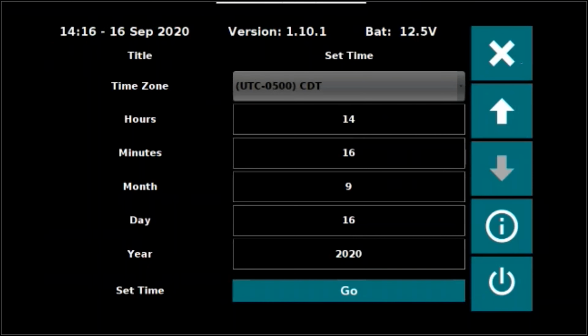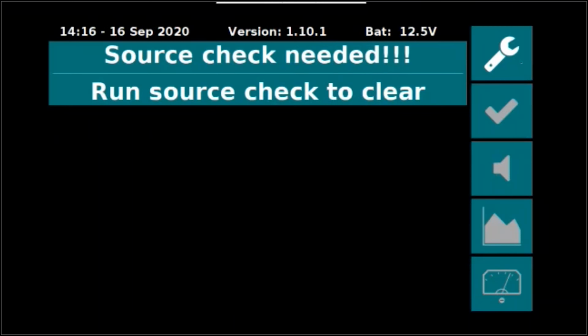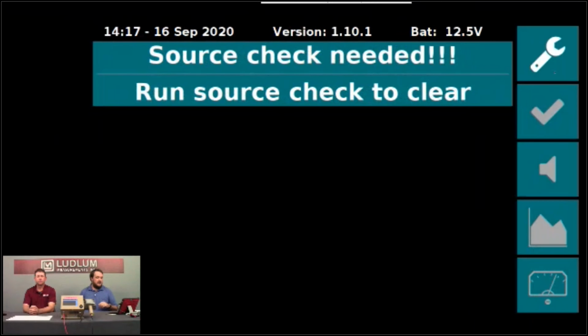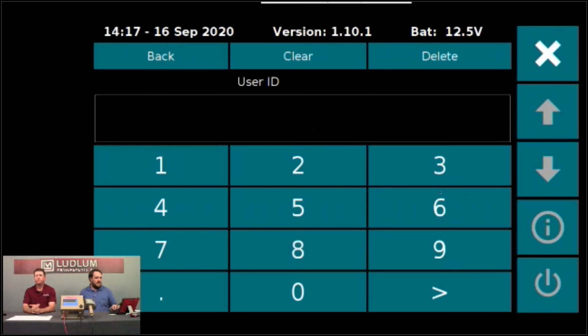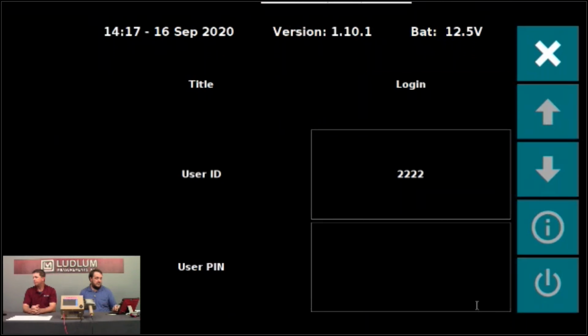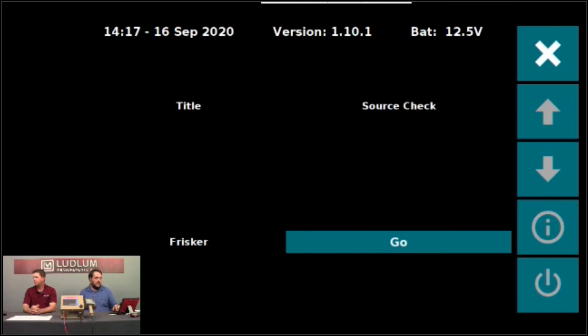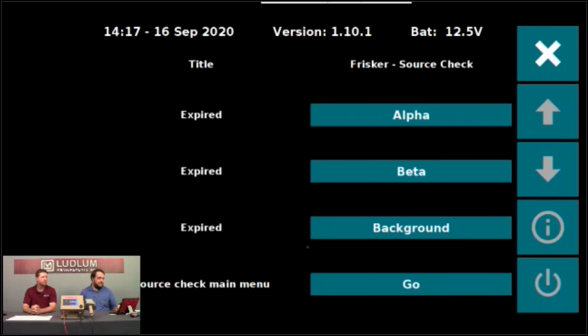So if I go back to the main settings, I've enabled the source check. So now the unit is unusable while the source check is expired. You can go into the settings menu again, or click the settings button, and this time go in as the source check user. And here you'll pick the detector you need to do a source check on. In this case, there's only the one. Again, on a hand-foot monitor, you may have a hand-foot and a Frisker, for example. So I'm going to pick the Frisker here. And then here we have each of the sources to check. Off to the left, they say expired, and you have each source that needs to be checked.